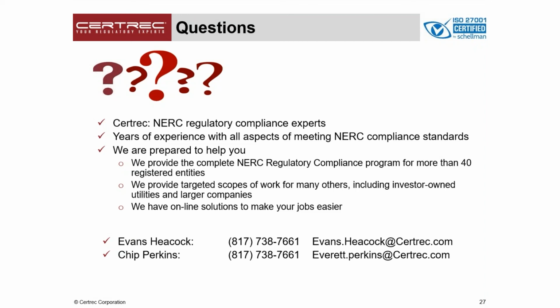Okay, great. I have another question here. Does the GO, the generator owner, receive the baseline settings from the TO, the transmission owner? How are the settings determined or received? Okay, so the GO does receive the baseline settings from the transmission operator. What they need to do is call up their transmission owner or service provider and ask them for the fault current at their substation. And once you get that, you want to document that information, that this is what you got from company X on day Y. As far as the settings go, that actually gets into your coordination study itself. If you're going to do a coordination study, you would need to take those and compare that fault level in your coordination study. It actually just goes straight in. I'd like to say we can get into more depth with that, but that's a little bit beyond where we're at with our particular conversation on this.